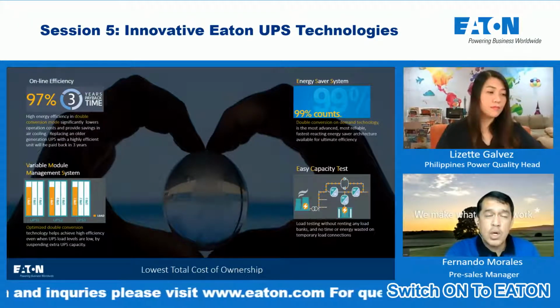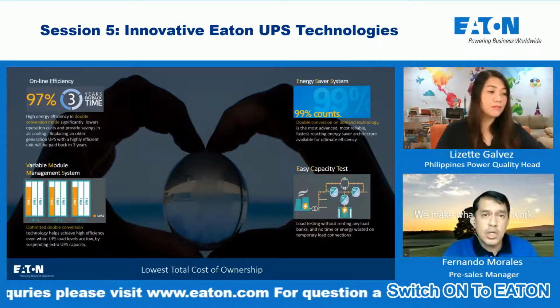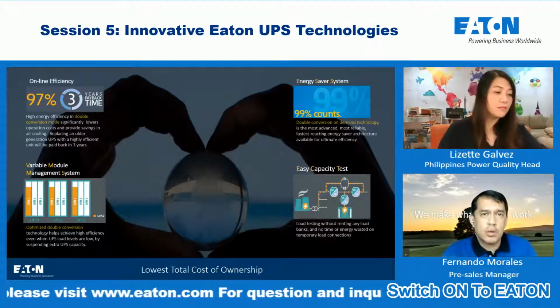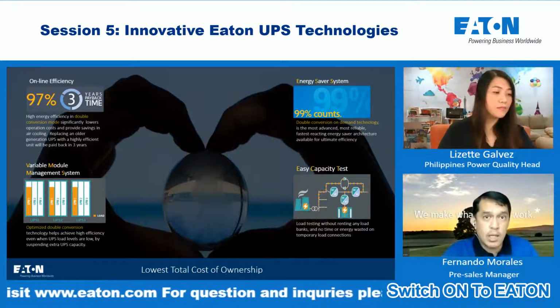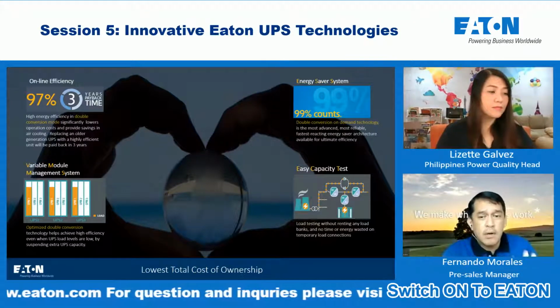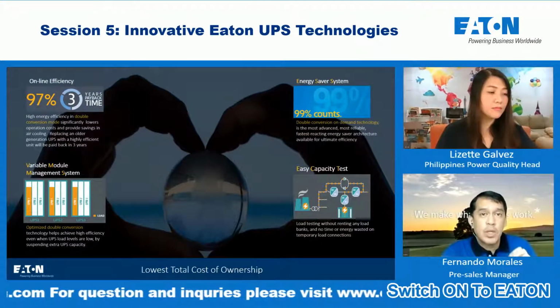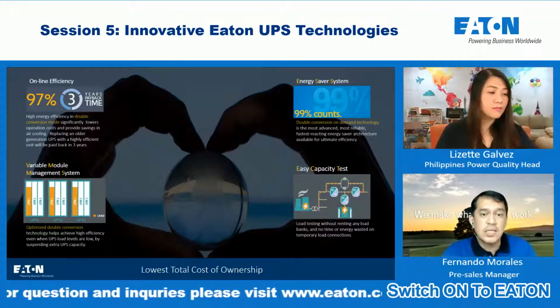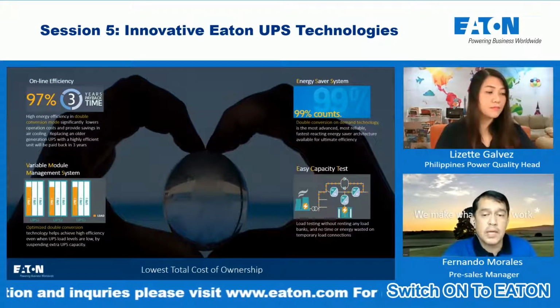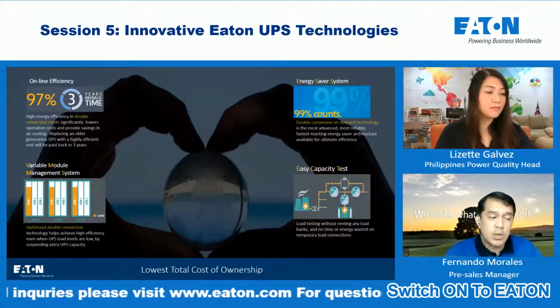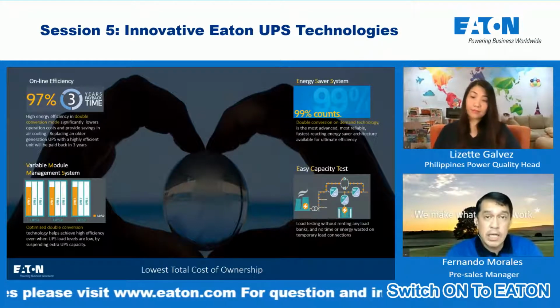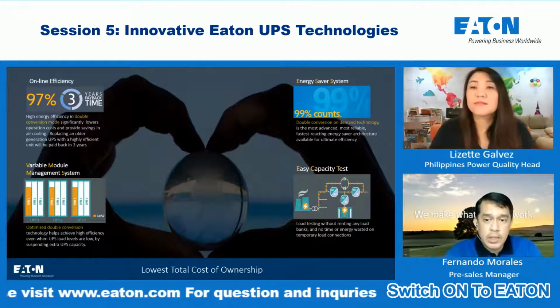We can use this technology if, for example, a customer requires a site acceptance test and wants to test the full load. We cannot test overload using ECT, but we can test the full load capacity of our system, and we can show this to our customer without using any load bank.